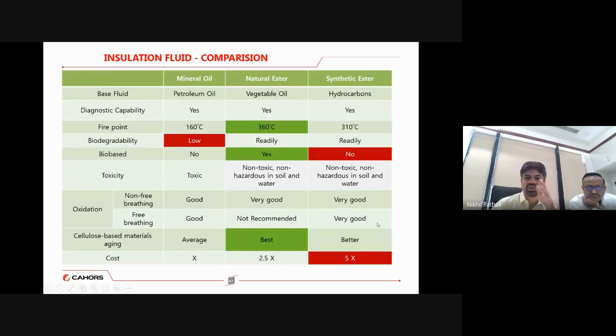So this is the difference of mineral oil and natural ester oil, and one more oil which is synthetic ester oil. So we are also encouraging customers and the energy auditors to encourage more and more natural ester oil, so that the fire hazard is eliminated from the power network, and the green power can also help us to deliver a risk-free and fire-free power as an approach, including the environmental benefits, because this oil is completely vegetable oil. It is non-toxic and non-hazardous. So even if it comes out of the transformer, it will not harm the environment, the insects, and there is no soil pollution. So it is very, very beneficial in all the aspects.